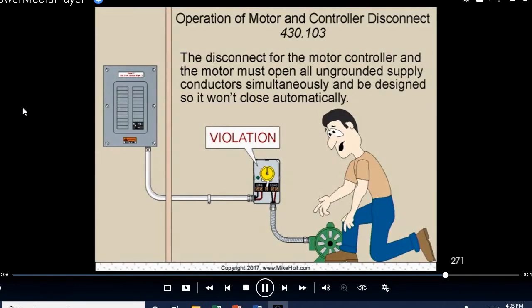Oh, by the way, the disconnect for the motor controller and the motor must open all ungrounded supply conductors simultaneously and be designed so it won't close automatically. You can't use a time clock as a disconnect, unless there was a setting in the time clock that would allow it to be rated as a disconnect. Otherwise you turn it off, and then all of a sudden you're working on it, and then what happens? The clock mechanism turns on because the line side is energized. So we have to be very careful.